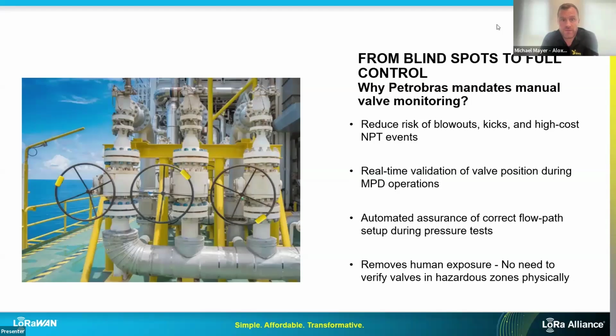Second, it provides real-time validation of valve position during MPD operations instead of relying on radio calls or memory during shift handovers. Operators can see the exact valve state in the doghouse or even in remote operation centers. Third, it gives automated assurance that the flow path is correct during these pressure tests.